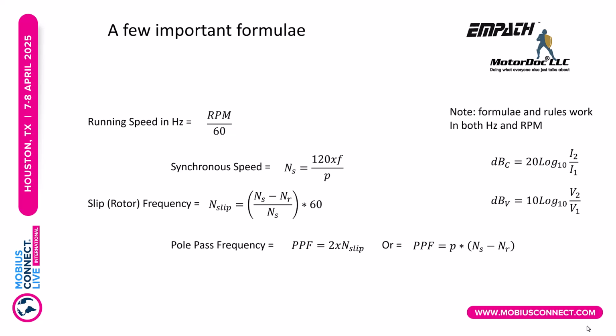So the nameplate running speed is when we're at full load. The NS is the synchronous speed, that is basically the speed at synchronous. So synchronous speed minus the actual running speed, divided by synchronous speed, times 60 gives me this slip frequency. Pole pass frequency is twice the slip, or some people do poles times the slip. So twice the slip frequency or poles times the slip. Both are the same number.